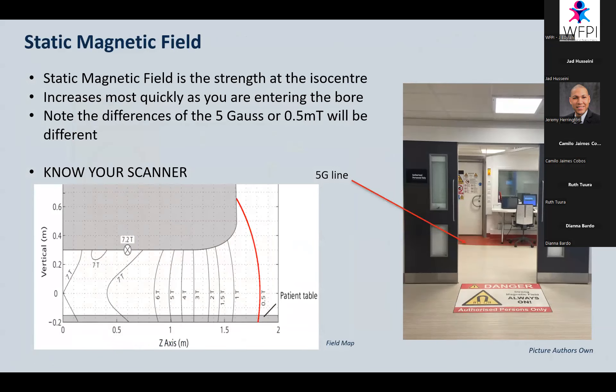The static magnetic field strength is at the isocenter of the bore, increasing rapidly as you move toward the center. The 5 Gauss line distance will differ for each scanner and must be measured — your physics team can do this. On our 7T, the control room is actually part of the MR environment, as the 5 Gauss line extends into it, visible where the flooring changes. Know your scanner and have that 5 Gauss line marked, as this is part of acceptance testing.